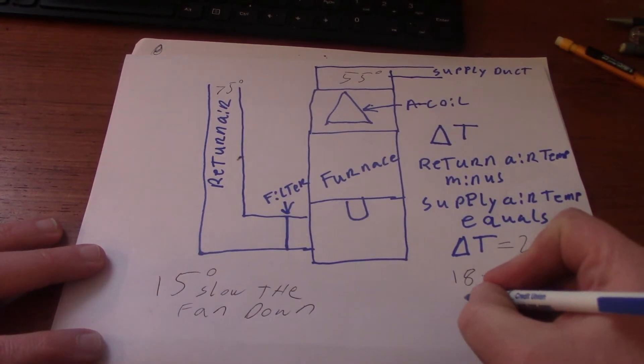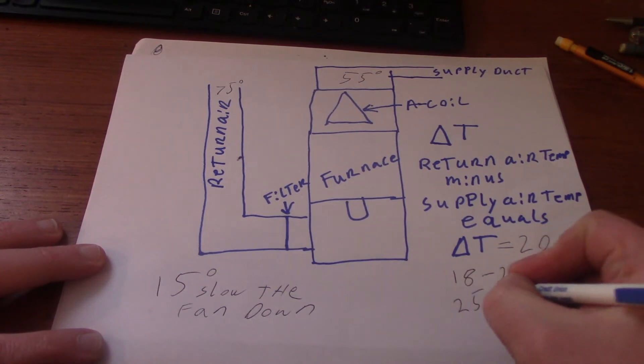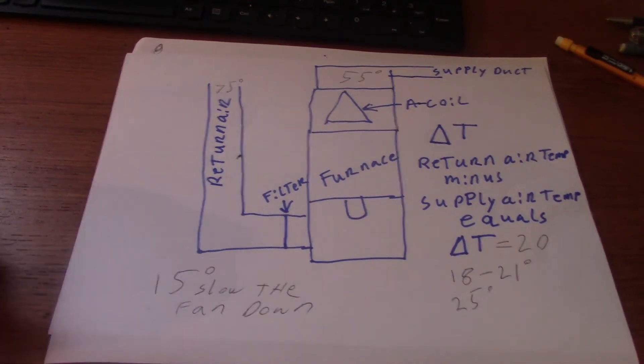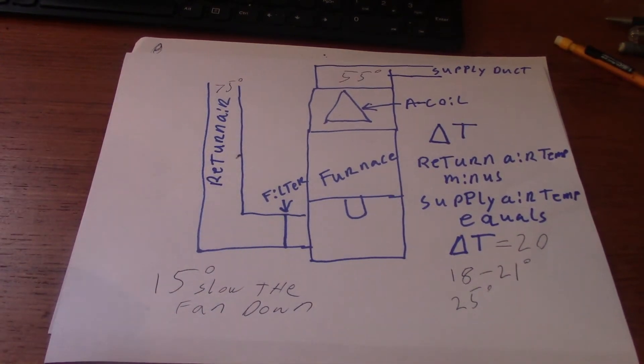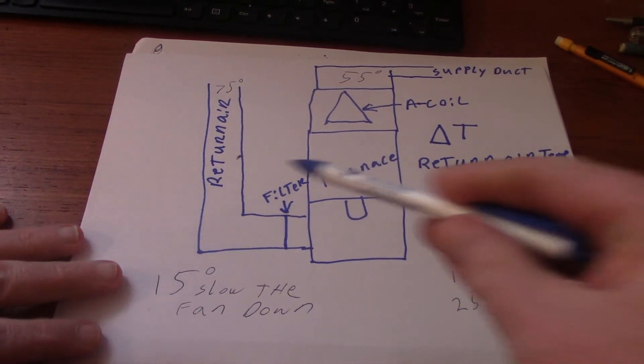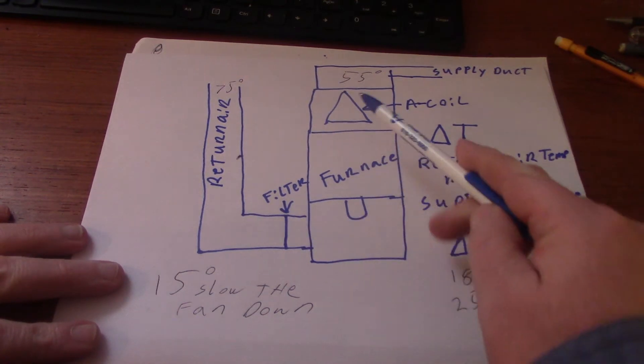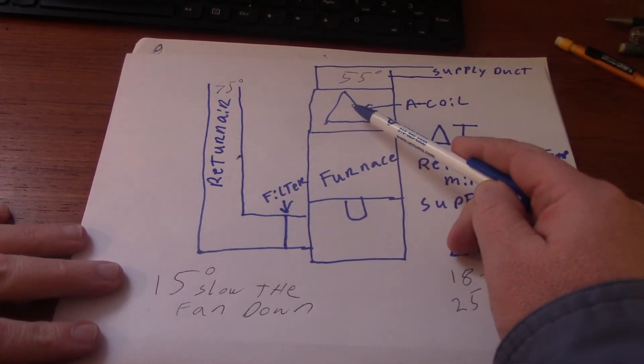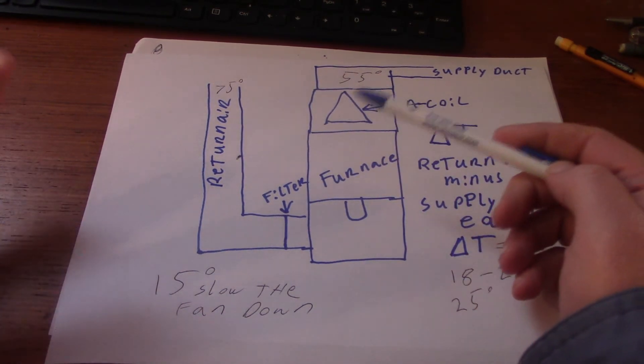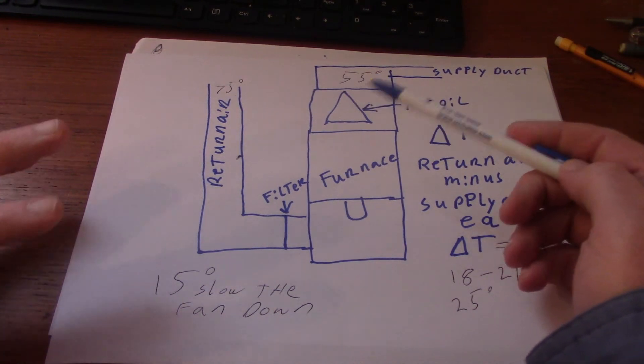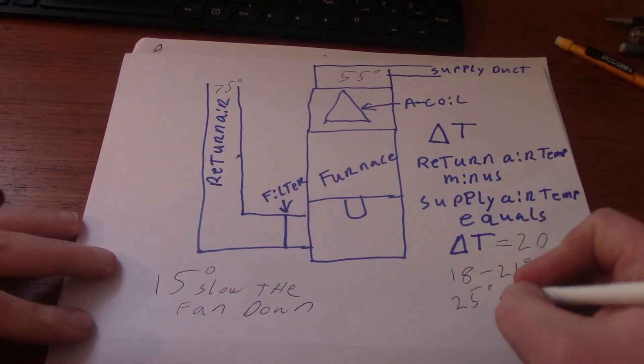If it comes up over here at, let's say, 25 degrees for your Delta T, the air is moving too slow. And you have to speed up the blower, possibly kick it on high speed, in order for it to function properly. Meaning the air is moving across the A-coil here, but it's moving too slow. It's just kind of hanging out there. And the evaporator here is absorbing too much heat from the air. Therefore you have a much colder temperature.